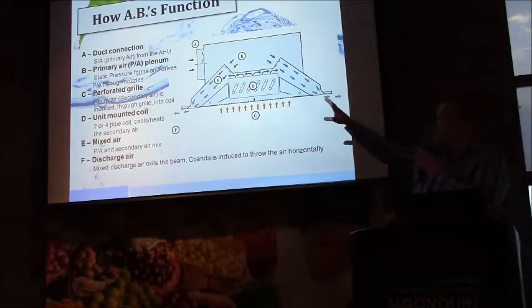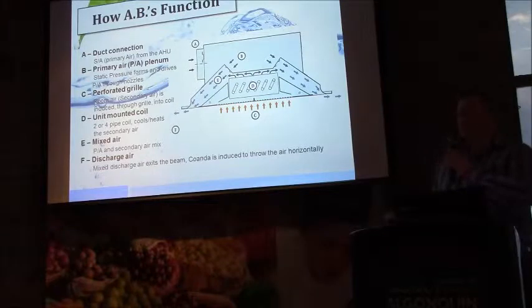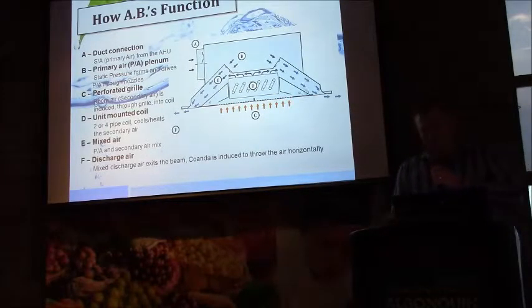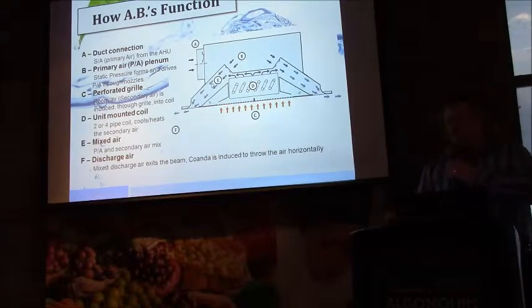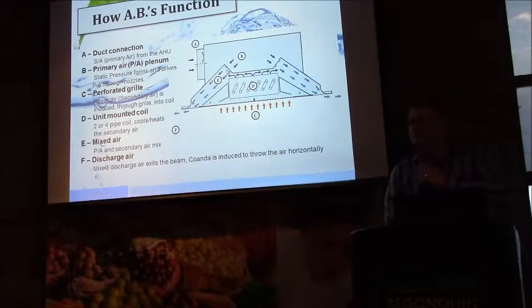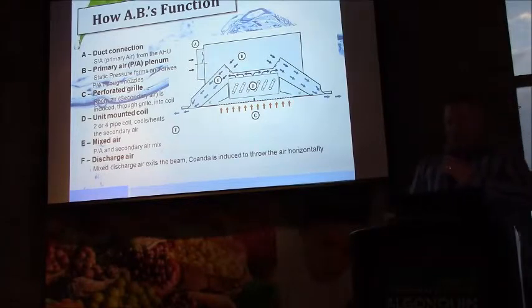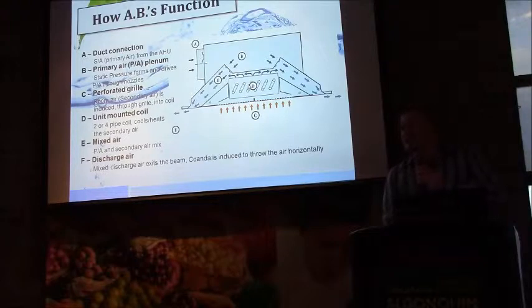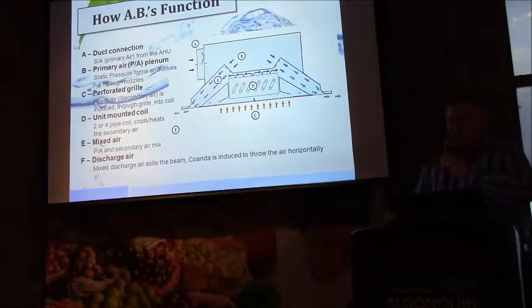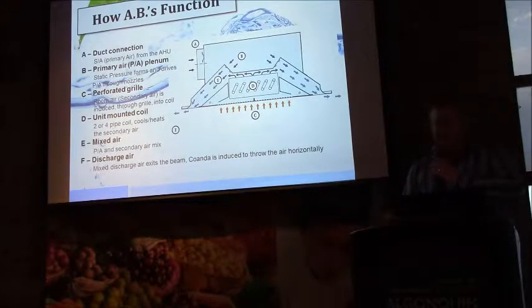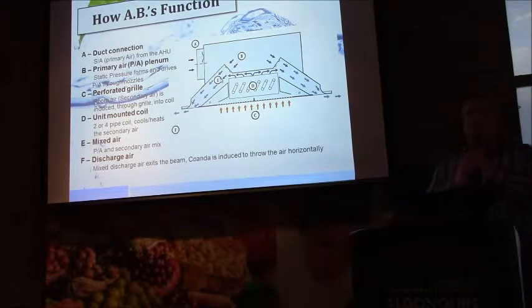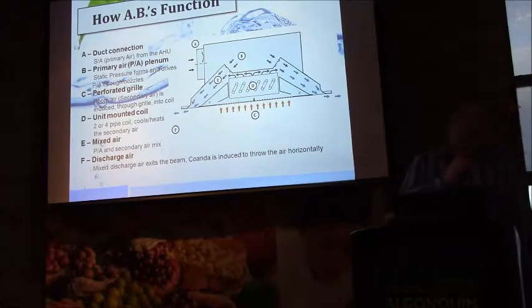The pressurized plenum then converts static pressure to a jet or a nozzle here at the sheet metal boundary between the plenum and the mixing chamber, and causes a low pressure zone at the root of the nozzle. And that low pressure zone helps to draw air in from the space that's rising through convective currents to pass across this coil at D that's held above the dew point of the space, and mixes in this mixing chamber here at E in ratios as little as 2:1 and as high as 6:1.